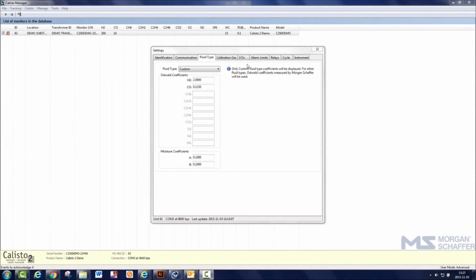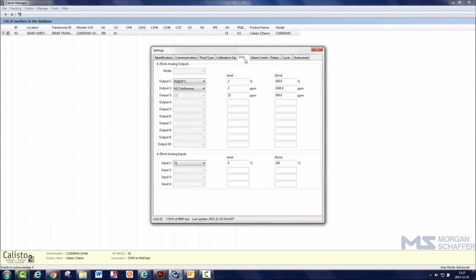I/Os. From the Settings window, the I/O tab is used to configure the 4-20 mA analog inputs and outputs to represent the desired gas, moisture, or temperature readings.